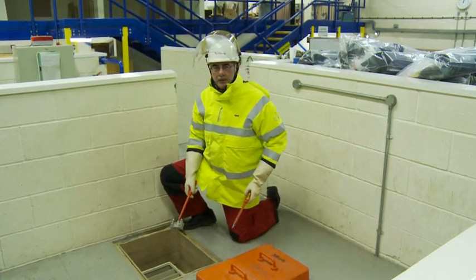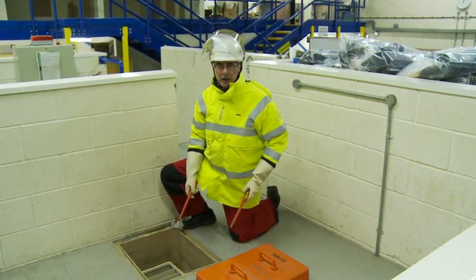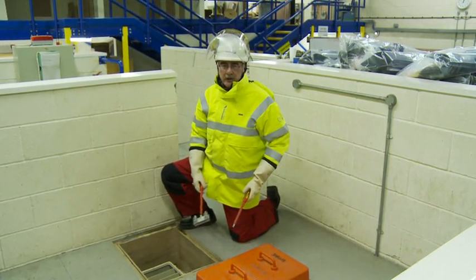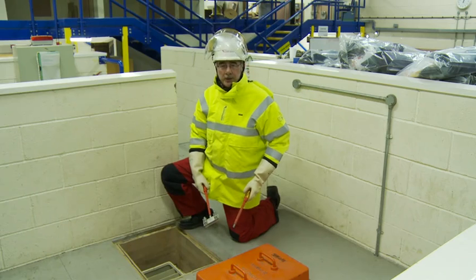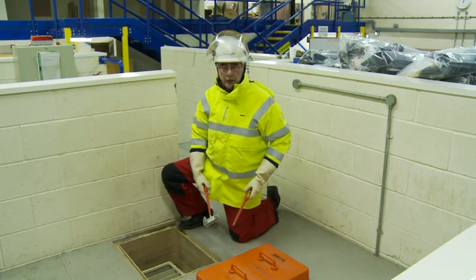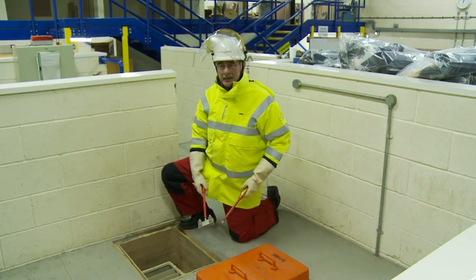Link boxes provide a bit of a challenge in terms of arc flash incident energy levels. That's because they often have multiple infeeds from different substations, and they also suffer from the box effect. In other words, the energy's only got one direction in which to go. So please don't dangle your feet inside the pit.